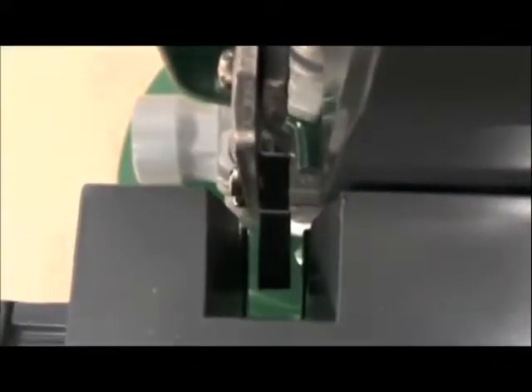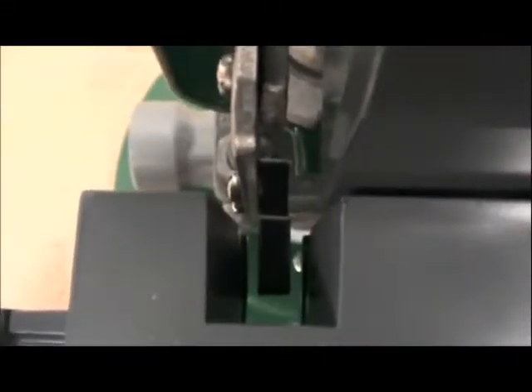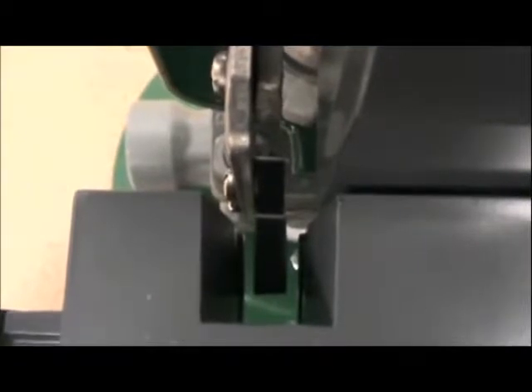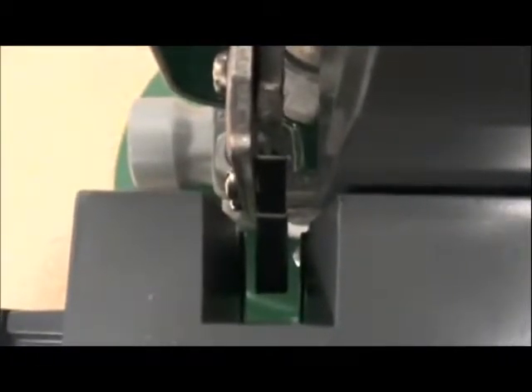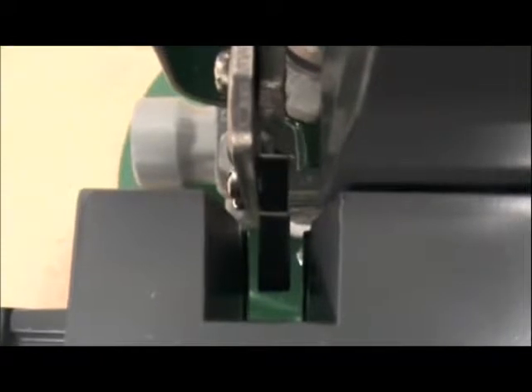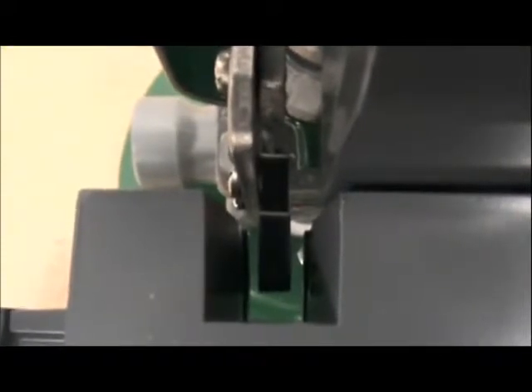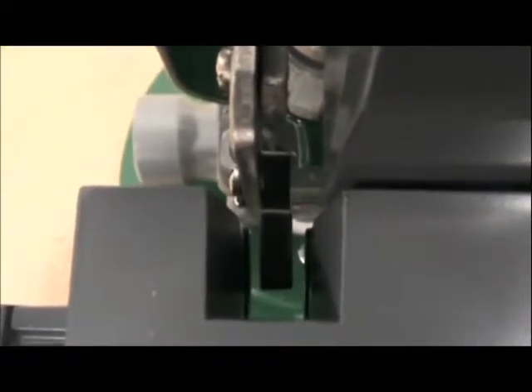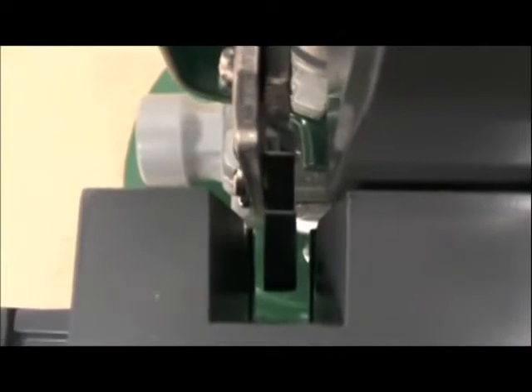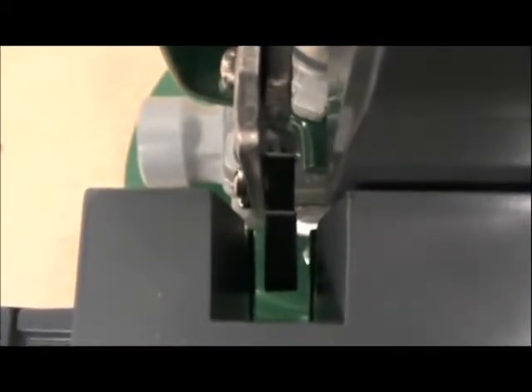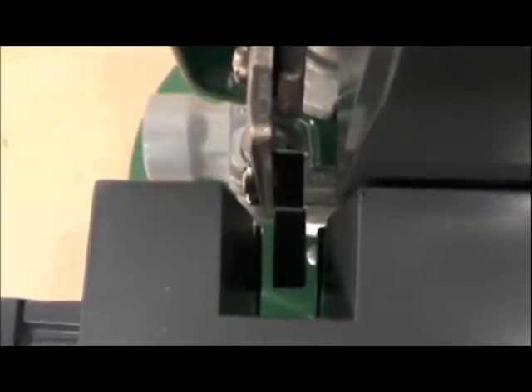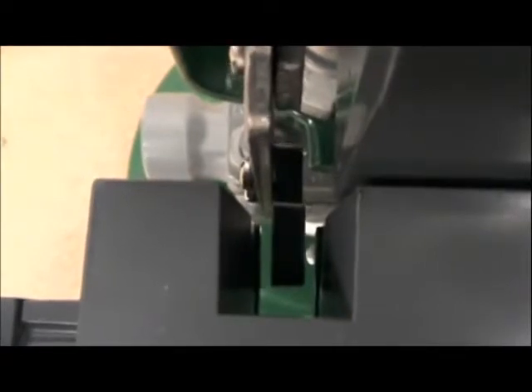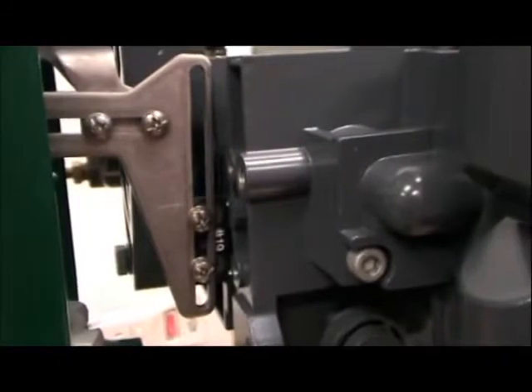Now we're looking down at the arm on the back side of the DVC-6200. Verify there's a nice equal spacing in between the arm and the channel on the back of the unit. We're going to stroke the valve up and down. We're going to make sure that we do not have any clearance or interference issues. We should also check from the side.